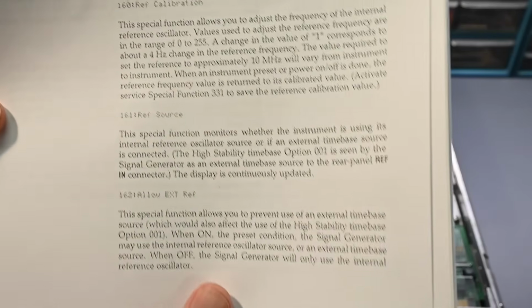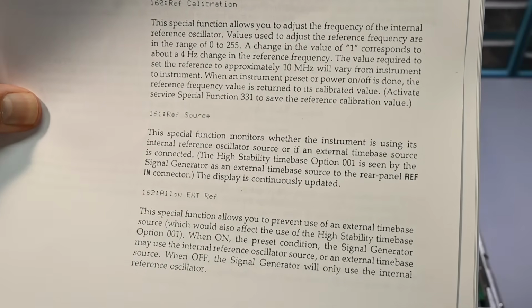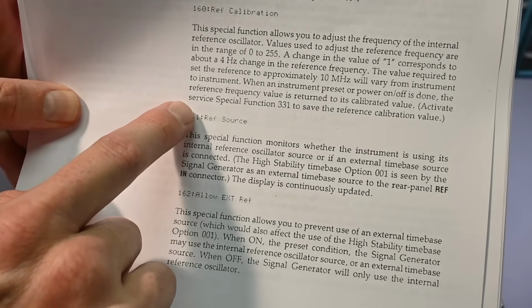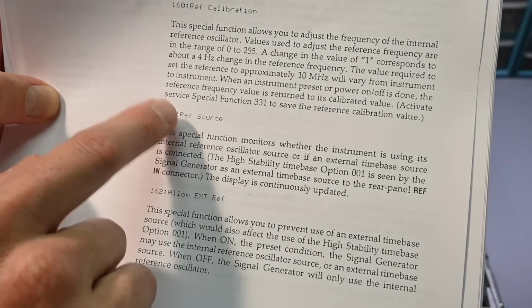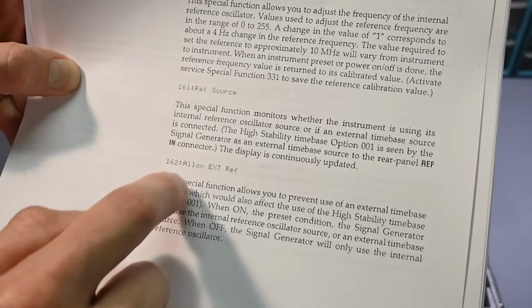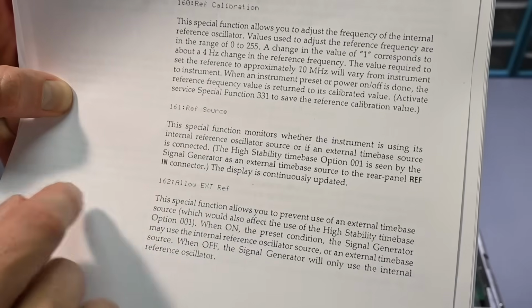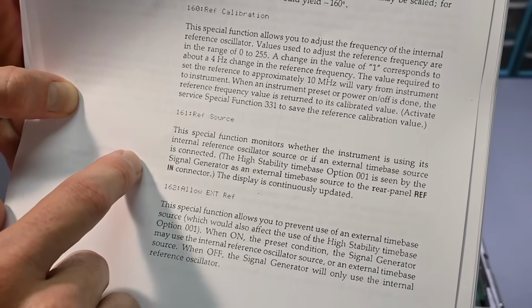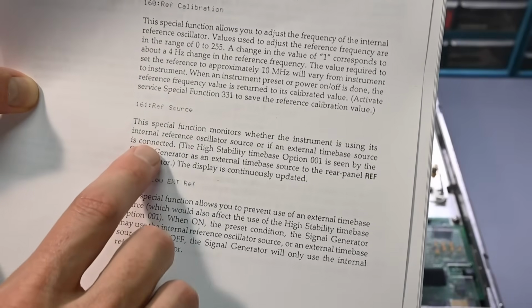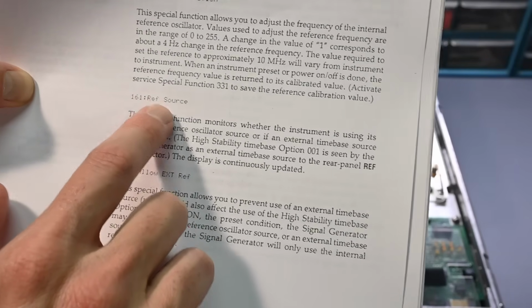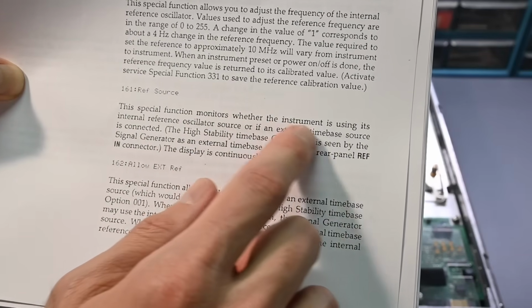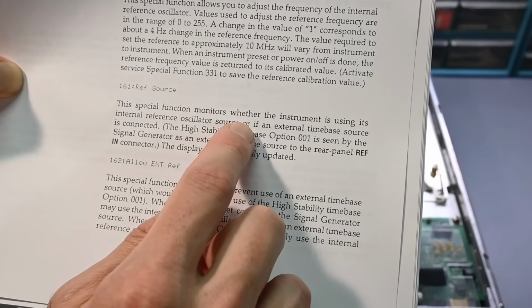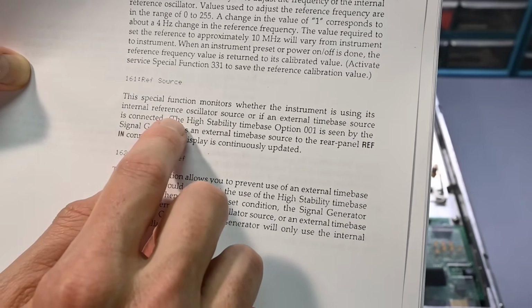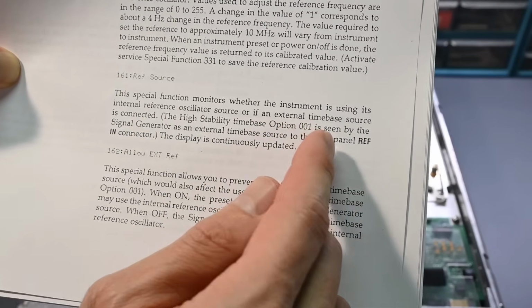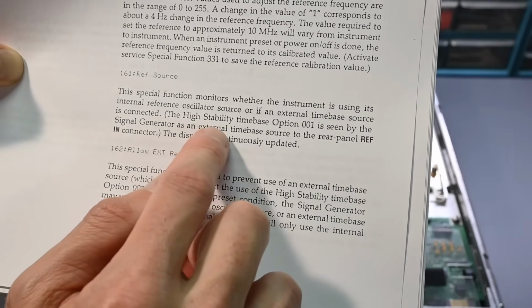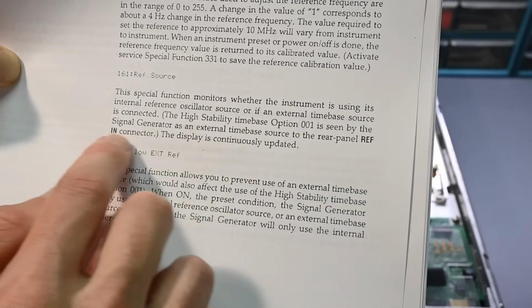So there's quite a few of these special functions, which are the front panel key that says special, and then you can enter a number. And if you don't know exactly which number you would use, you can just scroll through the actual text where it says reference source and allow external reference, things like that will come up on the screen, so you don't have to memorize these numbers. And there are many of these choices. But right here, take a look at this 161. It says reference source. Right here it says, this special function monitors whether the instrument is using its internal reference oscillator source or if an external time-base source is connected. And then in parentheses, the high stability time-base option 1, which we have, is seen by the signal generator as an external time-base source to the rear panel reference in connector.